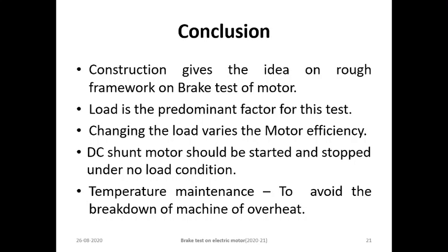And I told before, the variable load which we are using in the direct method is the main predominant factor of this test, which decides your motor efficiency. The motor efficiency mainly depends on the load changing of the motor, the load which we are giving with the spring balance.